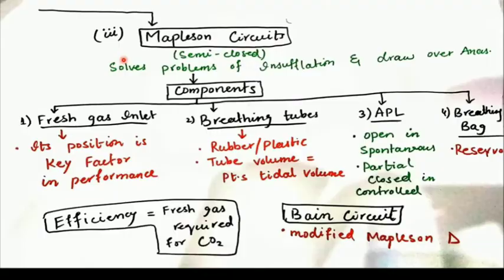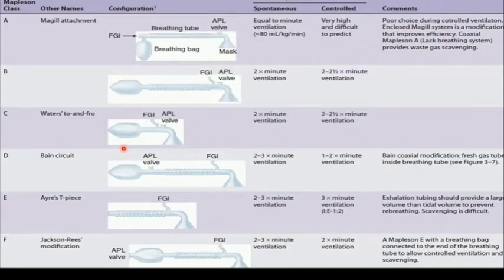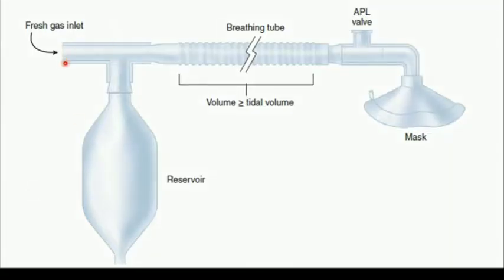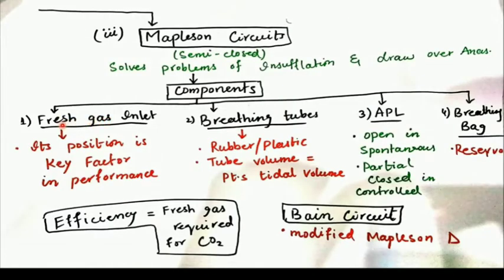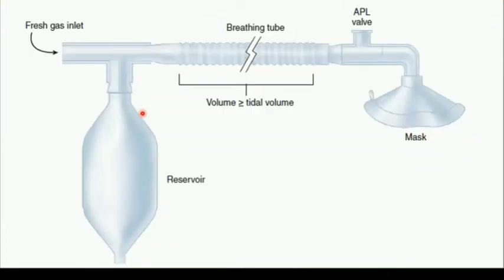The problems of insufflation and open drop anesthesia are solved by Mapleson circuits. Mapleson circuits are classified into classes A, B, C, D, E, and F. The parts of a Mapleson circuit are: a fresh gas inlet, a reservoir bag, a breathing tube, and an APL valve. The fresh gas inlet is the inlet for anesthetic gases, and its position is the key factor in the performance of the circuit.